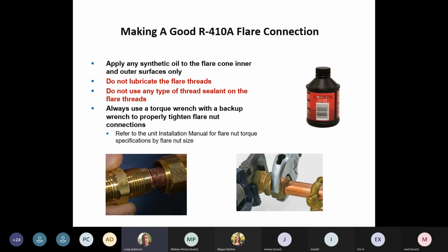Do not go out and get a bigger wrench. It's not solving the problem. It's actually creating more of a problem. It's probably going to mushroom your flare or crack the flare nut. You should not need a lot of force to do a 410A flare with a couple of Crescent wrenches and a torque wrench.